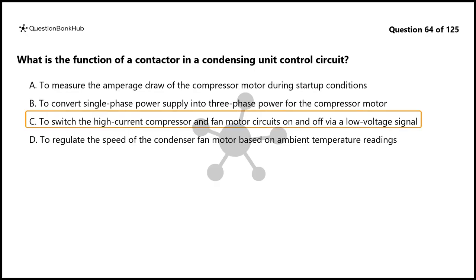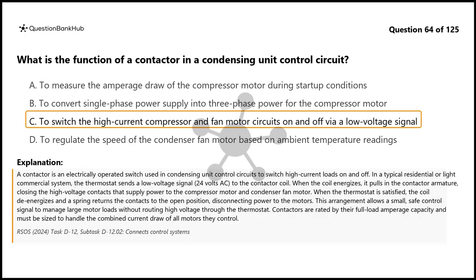The correct answer is C. A contactor is an electrically operated switch used in condensing unit control circuits to switch high-current loads on and off. In a typical residential or light commercial system, the thermostat sends a low-voltage signal, 24 volts AC, to the contactor coil. When the coil energizes, it pulls in the contactor armature, closing the high-voltage contacts that supply power to the compressor motor and condenser fan motor.